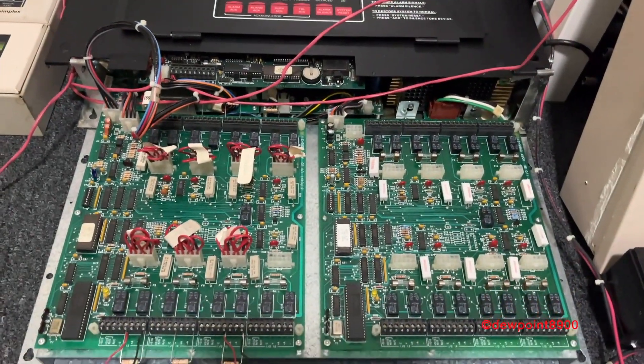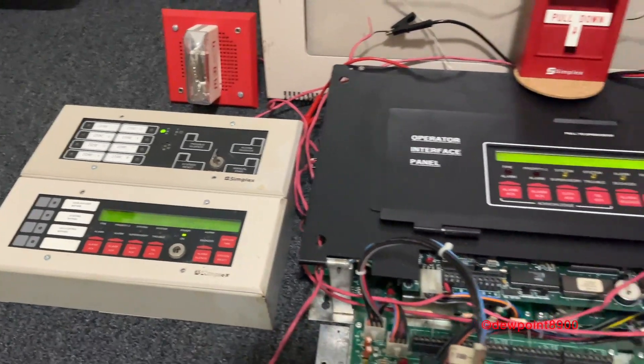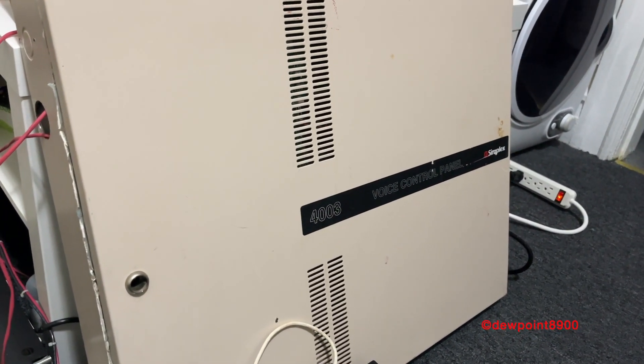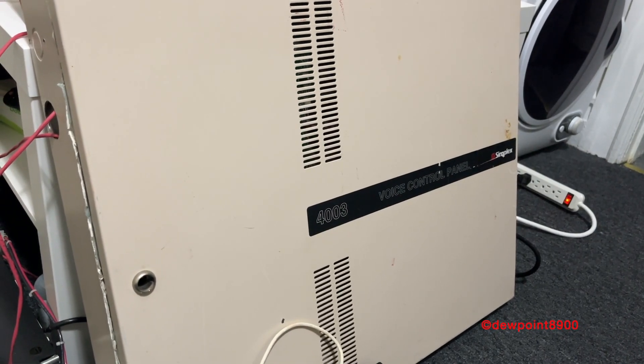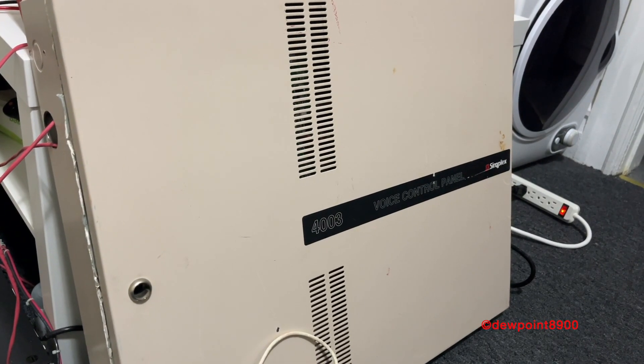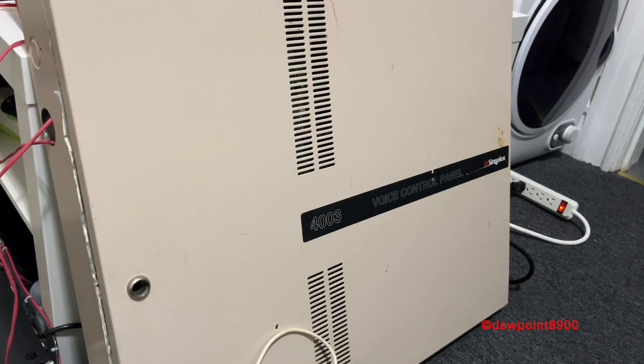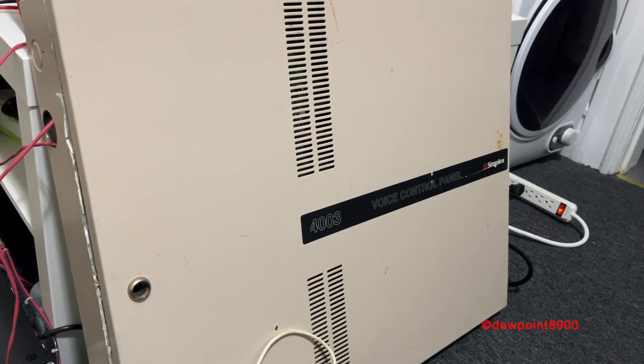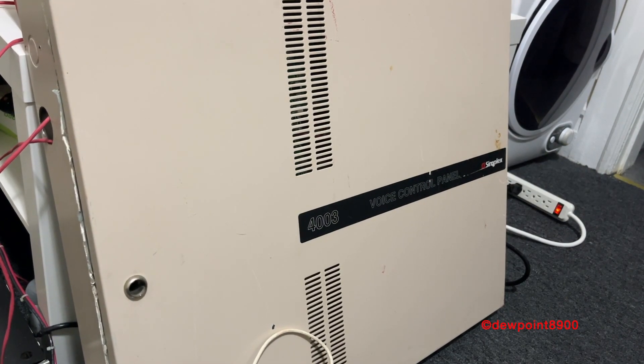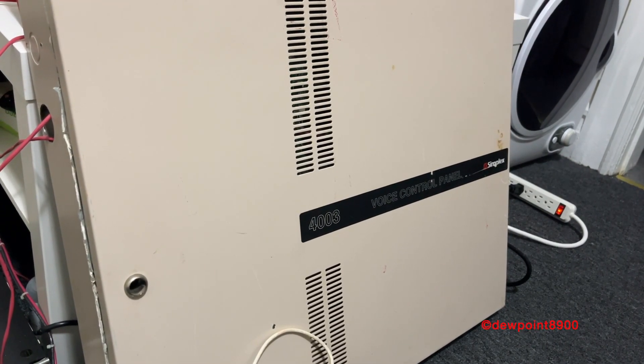Down here are some expansion cards, and over here are some annunciators. The 4003 Voice Control Panel provides tone and voice options to a host fire alarm control panel. These were first produced in the early 90s and have been presumably discontinued in favor of the 4003 EC. The 4003 has several different audio tones, which could be selected via dip switches, as well as pre-recorded messages, which could be customized as needed.